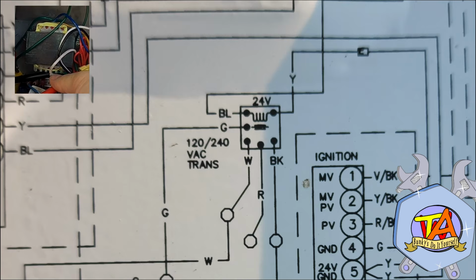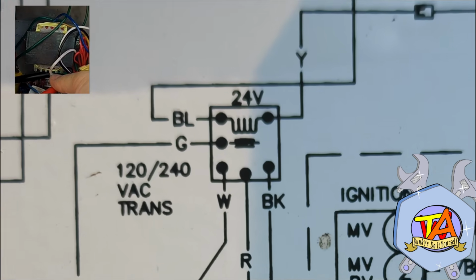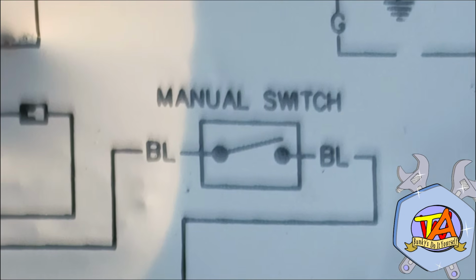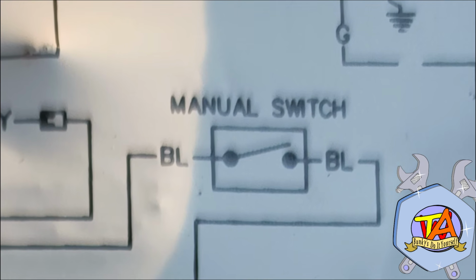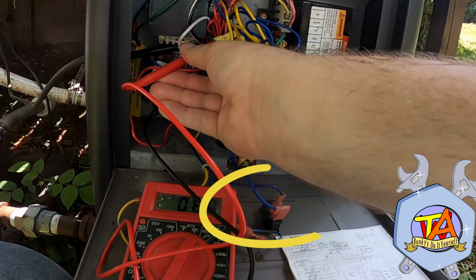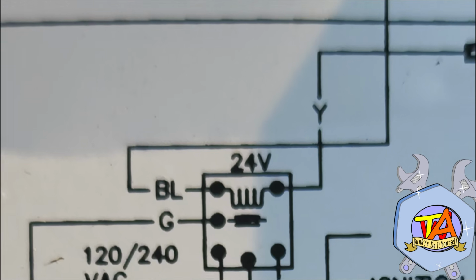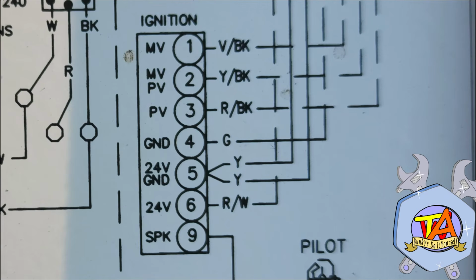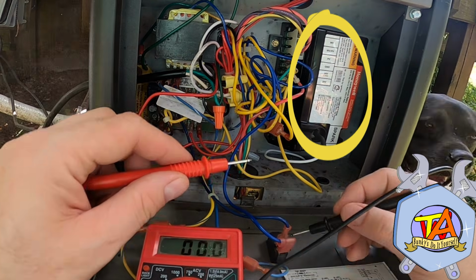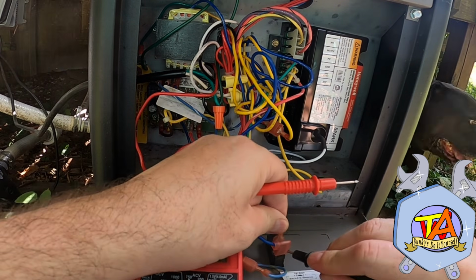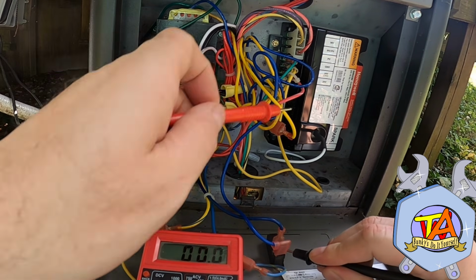Now we need to find out whether the transformer is working. So we need to follow these blue and yellow wires. This blue wire goes to a manual switch. This is this switch right here. I've had switches go bad in the past, so it's best to check both sides. Now the yellow wire goes to this ignition board. It's this big guy over here. So I go ahead and test the switch and make sure that there's 24 volts going to the circuit, which we have about 26 volts.